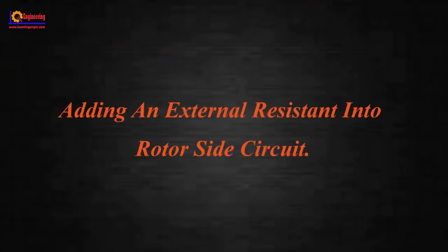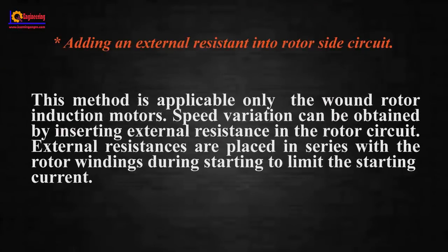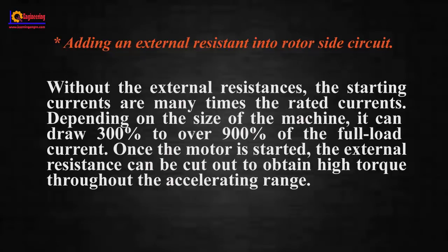Adding an external resistance into rotor side circuit: this method is applicable only for wound rotor induction motors. Speed variation can be obtained by inserting external resistance in the rotor circuit. External resistances are placed in series with the rotor winding during starting to limit the starting current. Without the external resistance, the starting currents are many times the rated current. Depending on the size of the machine, it can be 300% to over 900% of the full load current.